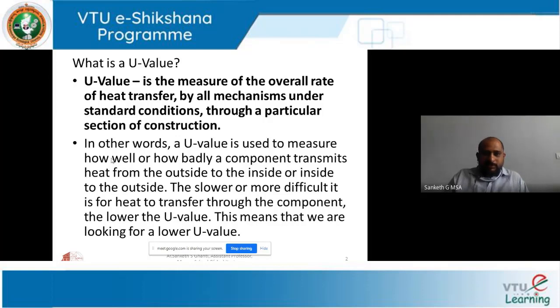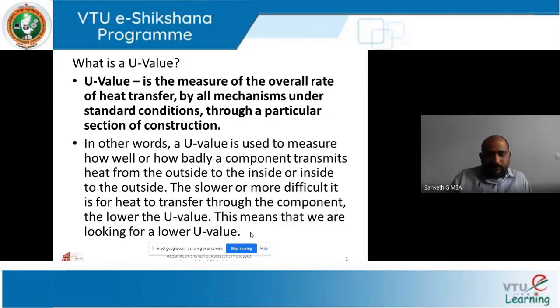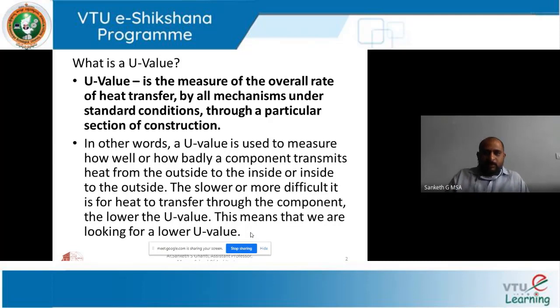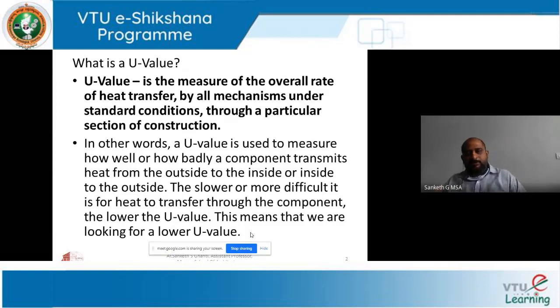In other words, U-value is used to measure how well or how badly a component transmits heat from outside to inside or inside to outside. The slower or more difficult it is for heat to transfer through the component, the lower the U-value. This means we are looking for a lower U-value. People in hot climates and even cold climates are looking for a lower U-value. It is only in moderate climates that you can go for a higher U-value. Lower U-value means less heat transfer; higher U-value means more heat transfer.